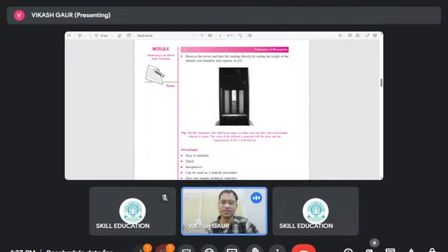Don't add distilled water in a frequent way. Add distilled water slightly, one drop at a time. One drop added, then mix; one drop added, then mix; one drop added, then mix. So we can compare the color of the hemoglobinometer tube and the comparator box. Then remove the stirrer and take the reading directly by noting the height of the hemoglobinometer lining.